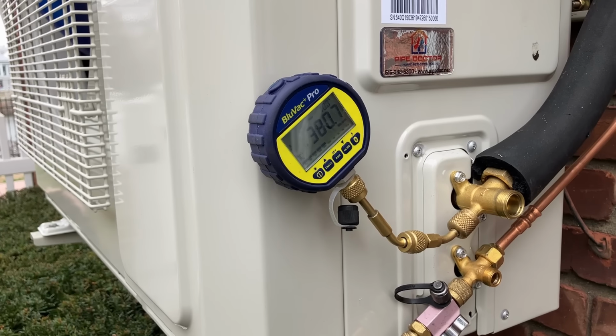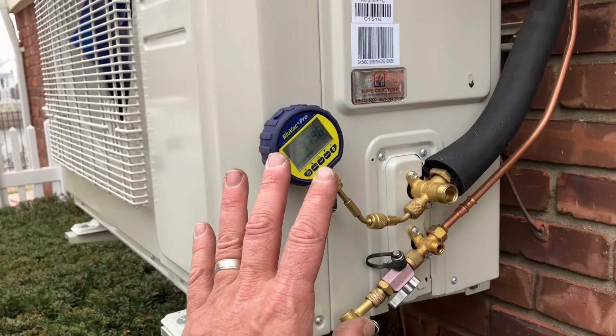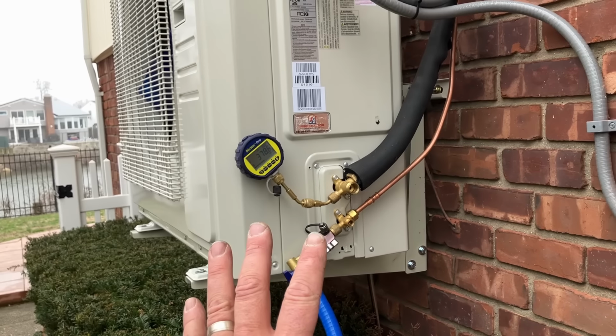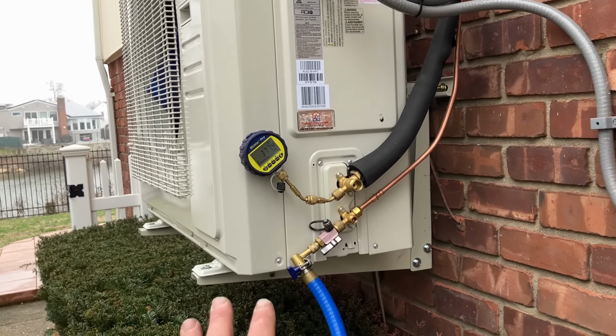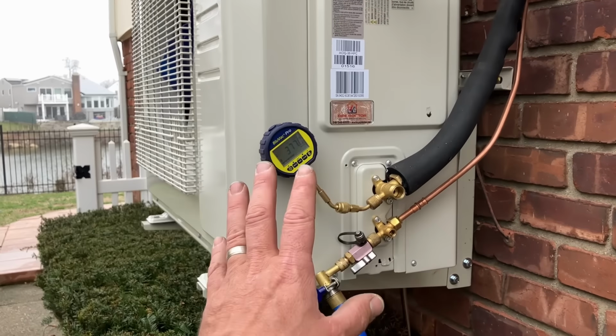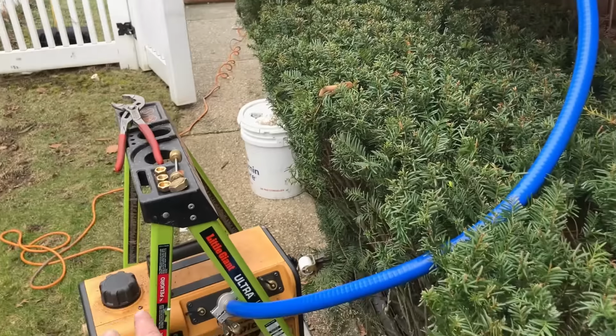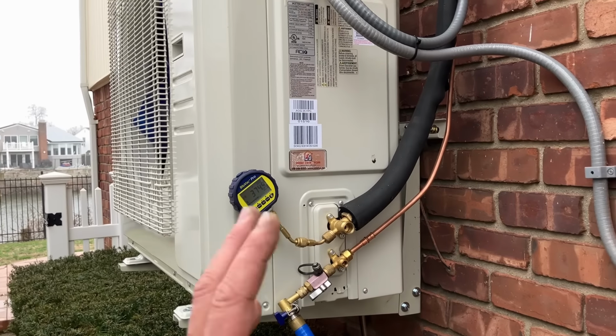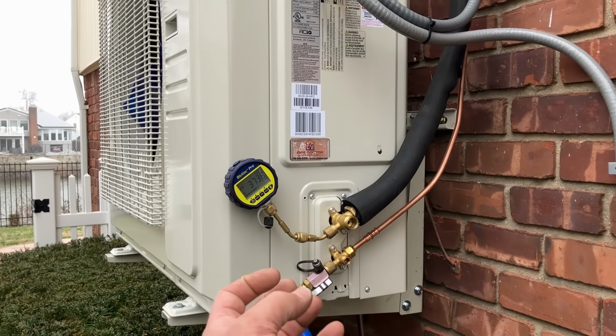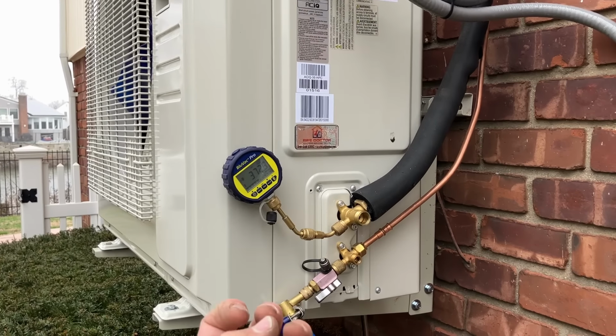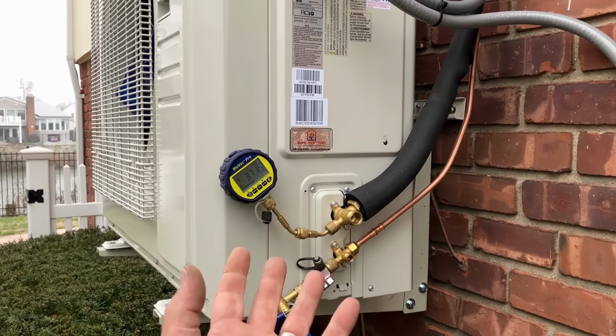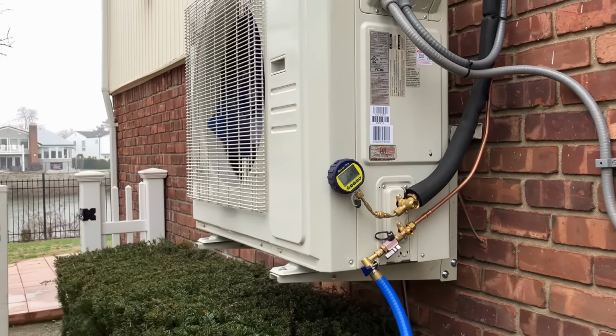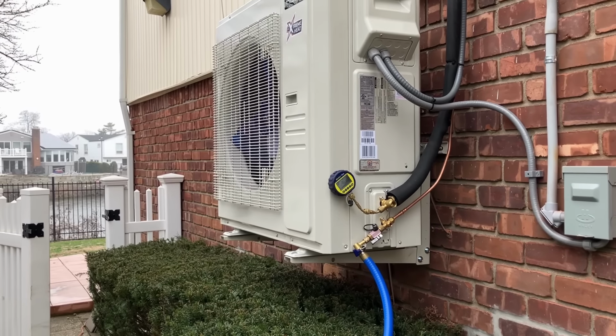380 microns and dropping. Now, industry standard is 500 microns. If you're an HVAC tech, hopefully you have a micron gauge and a vacuum pump, but you know that 500 is the minimum we need to bring the system down to in a vacuum to have a nice, tight, and most importantly, dry system.